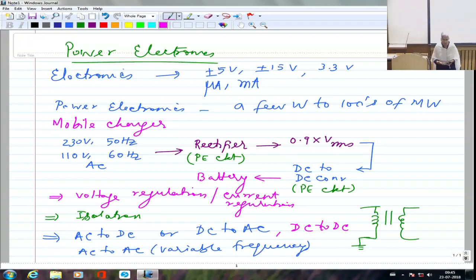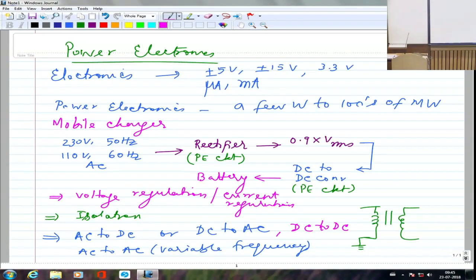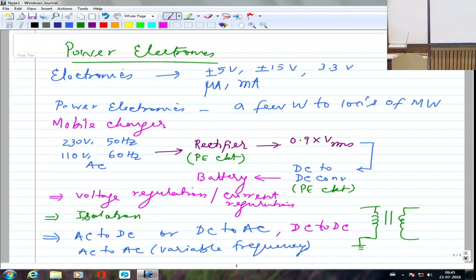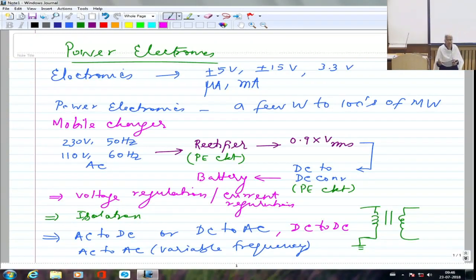One example is the mobile charger. Another is the variable frequency induction motor drive you did in the lab. Inside that box was a rectifier converting 50 Hz AC to DC, followed by an inverter converting that DC into variable-frequency AC. That is a typical adjustable speed drive — an AC-to-DC converter followed by a DC-to-AC inverter.